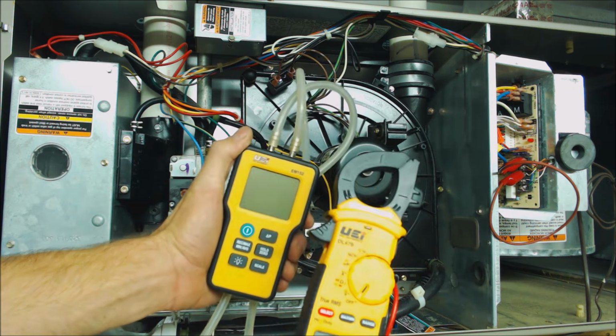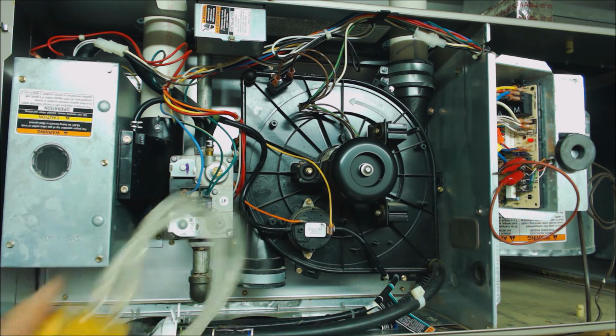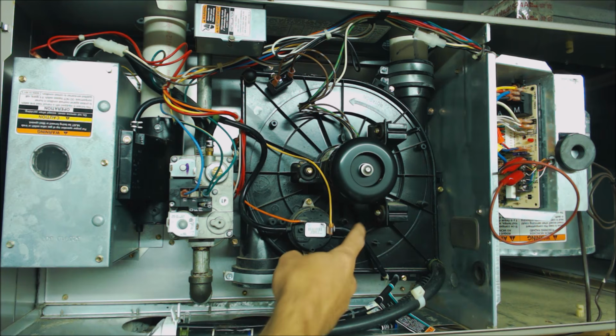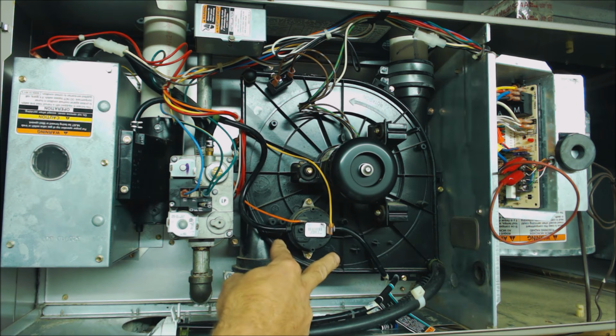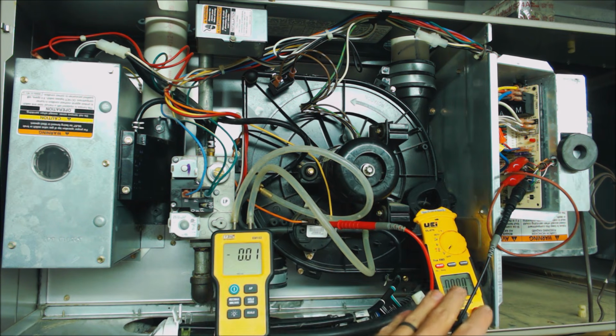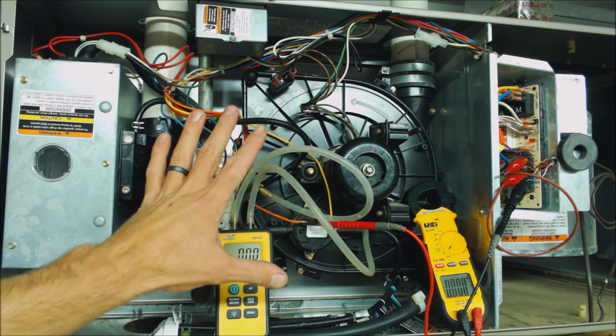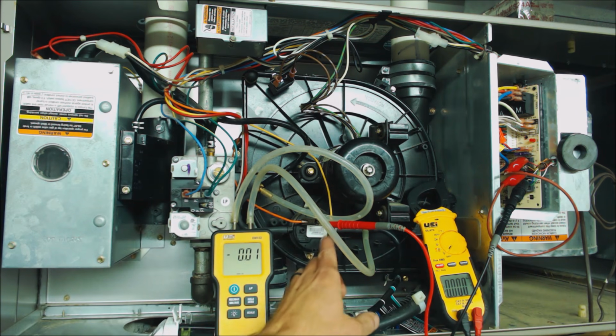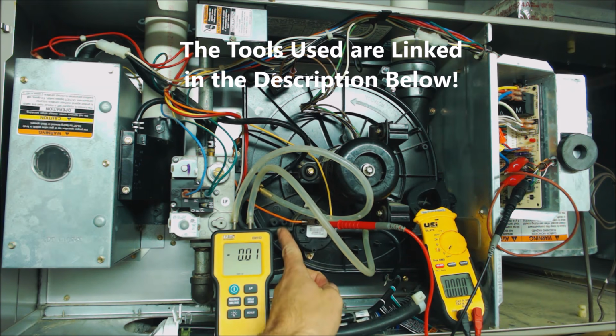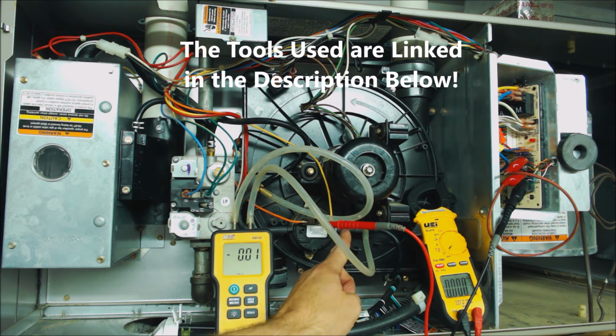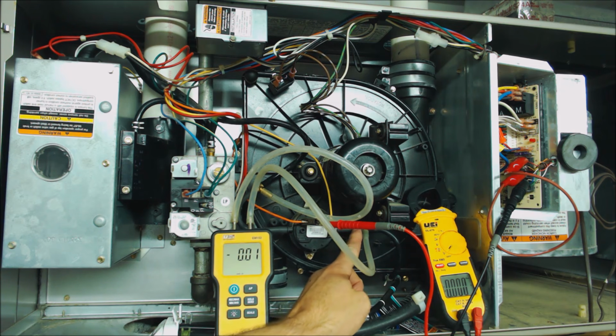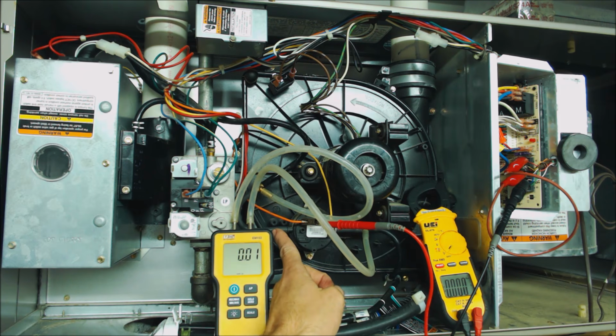manometer. So this is a 2-port digital manometer because we need a differential reading since there's 2 hoses across the pressure switch. So we have our multimeter and our digital manometer all hooked up. I'll go over that in a second. But on this pressure switch, since there's 2 sets of tubing, one's the positive side and one's the negative side, that does not mean that this is actually positive. It just means that this is in a deeper vacuum than the vacuum on this side.